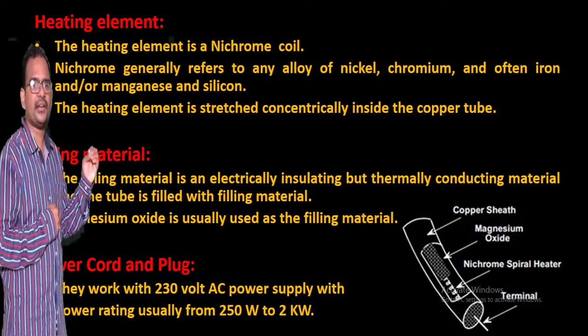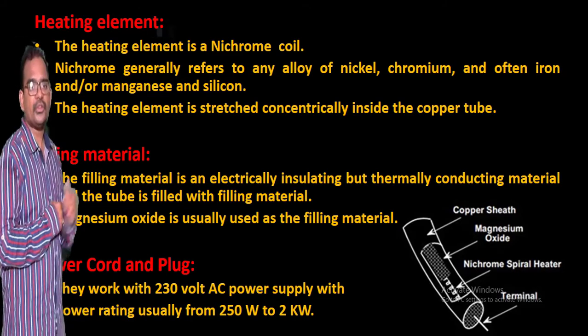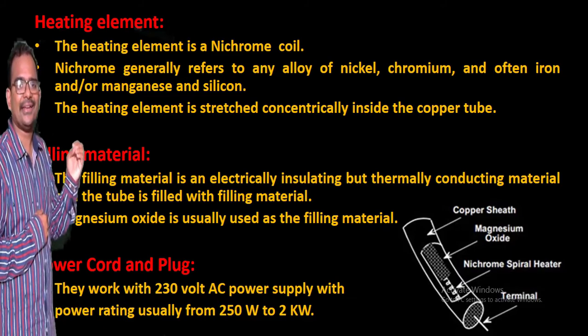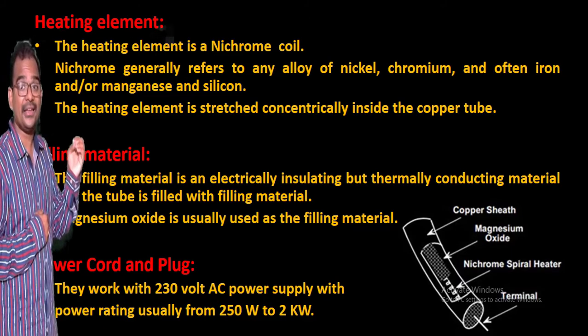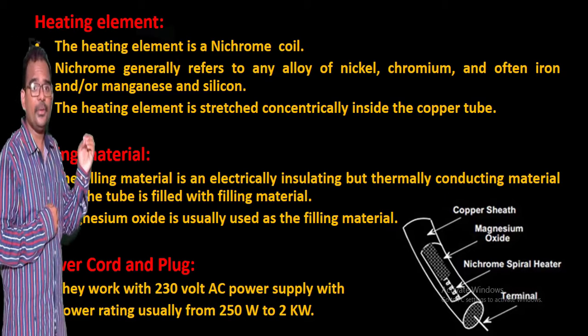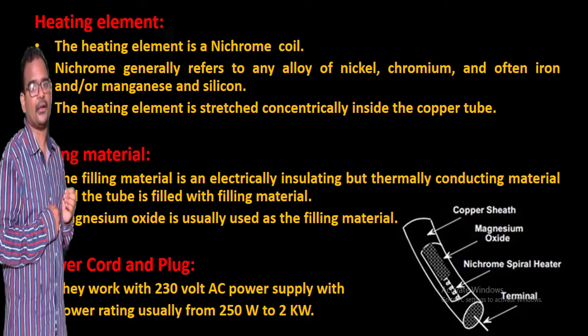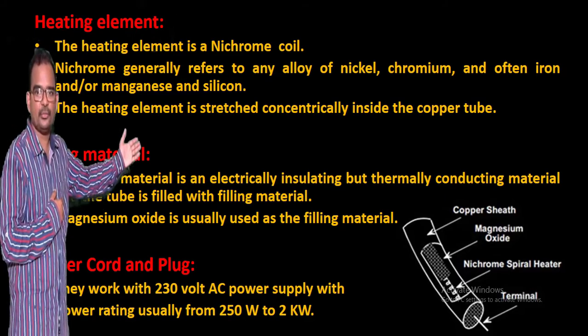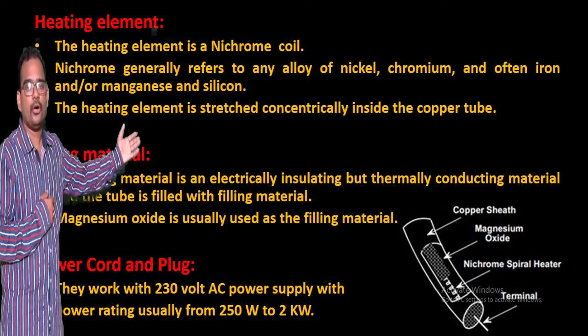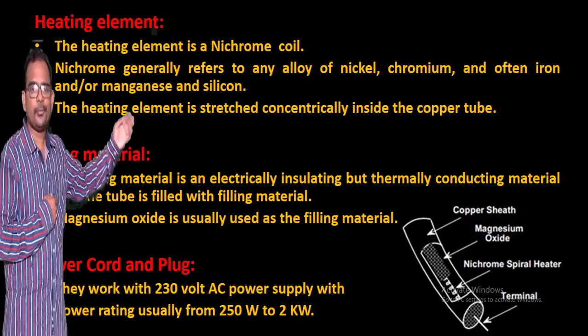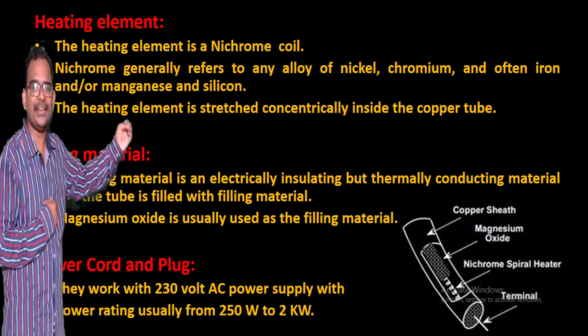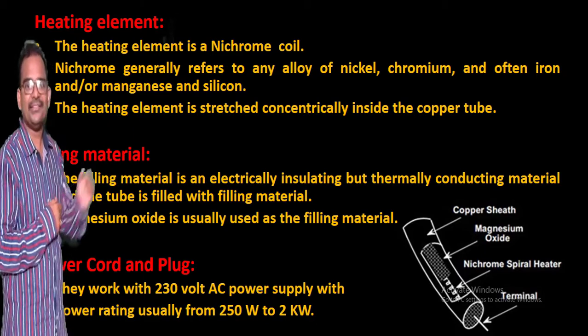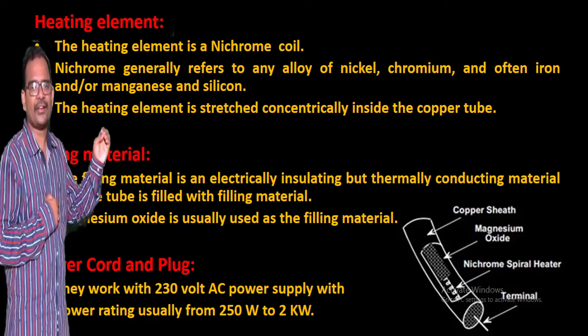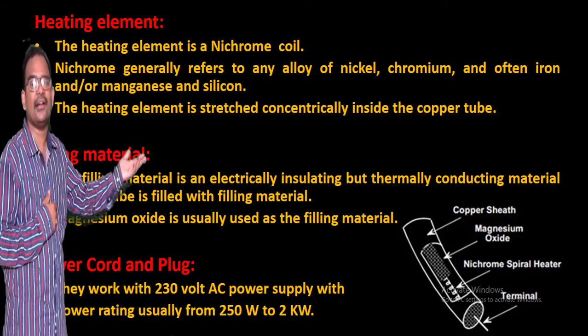The third part is the filling material, which is electrically insulating but thermally conducting, and the tube is filled with it. The copper tube is filled with magnesium oxide, which is generally used as a filling material in immersion heaters, acting as an insulator for electricity while being a conductor for heat.